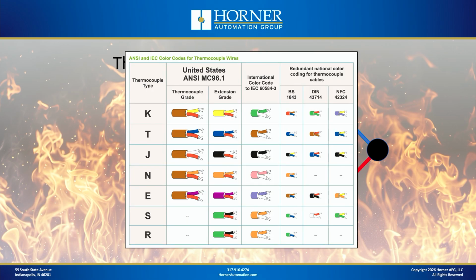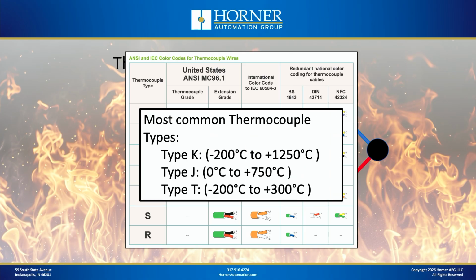Once again, I mentioned the fact that different combinations of metals will be different types of thermocouples. Here's a chart showing some of the most common thermocouple types available on the market today. And one thing that we'll talk about here in a minute is that not only do you have the thermocouple grade material, but you also have extension grade material. What is that all about? Well, we'll be covering that here shortly. Now, in terms of the most common types used from this chart, you're basically looking at type K, which is the most widely used. You can see the temperature range there. Type J and type T. Type T is very popular with really cold temperatures, for instance.